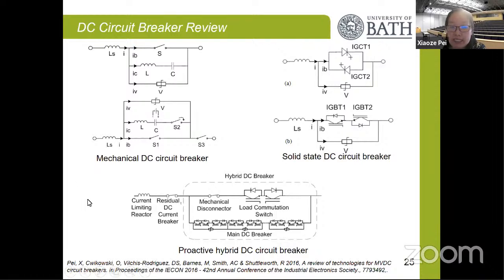What it means is that during normal operation, the current goes through this mechanical switch. So this is a low losses path. When the fault happens, this load commutation switch opens first, which means the current in the mechanical switch reduces to zero and is diverted to the main DC circuit breaker using the solid state devices. So the mechanical switch can open without current and without arc. Once it is able to withstand the system voltage, we can open the solid state DC circuit breaker.